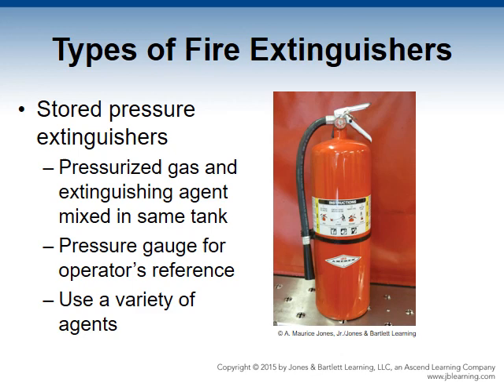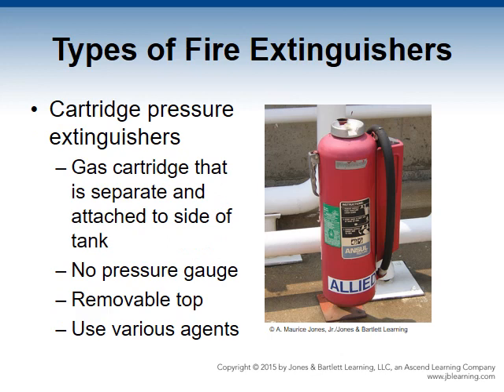Stored pressure extinguishers have the pressurized gas and extinguisher agent mixed in the same tank. The gas — air or nitrogen — is stored above the agent, keeping constant pressure on it, which forces the agent out through the nozzle or horn. An operator can determine if there is sufficient pressure by looking at the pressure gauge. These extinguishers use a variety of agents such as water, antifreeze, wetting agent, loaded stream, foam, dry chemical, wet chemical, dry powder, or halon.